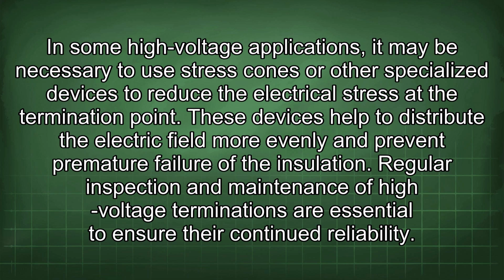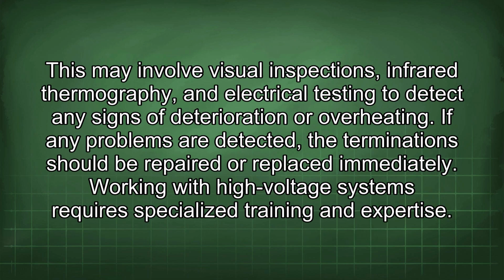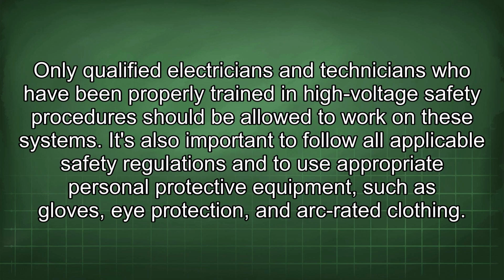Regular inspection and maintenance of high-voltage terminations are essential to ensure their continued reliability. This may involve visual inspections, infrared thermography, and electrical testing to detect any signs of deterioration or overheating. If any problems are detected, the terminations should be repaired or replaced immediately. Working with high-voltage systems requires specialized training and expertise. Only qualified electricians and technicians who have been properly trained in high-voltage safety procedures should be allowed to work on these systems. It's also important to follow all applicable safety regulations and to use appropriate personal protective equipment such as gloves, eye protection, and arc-rated clothing.